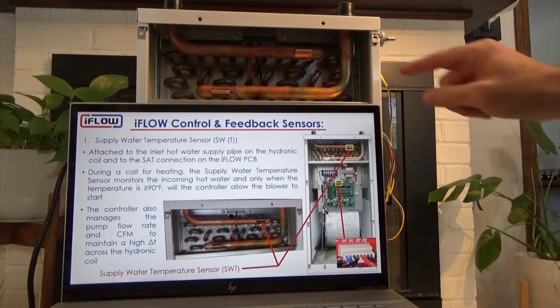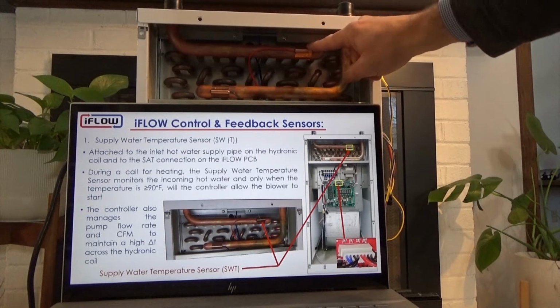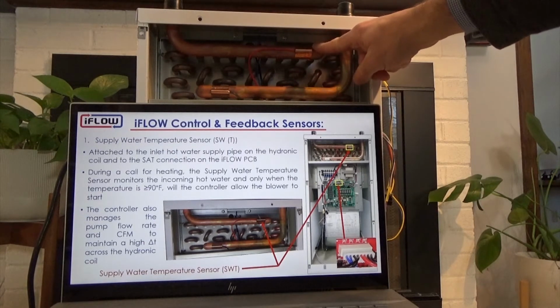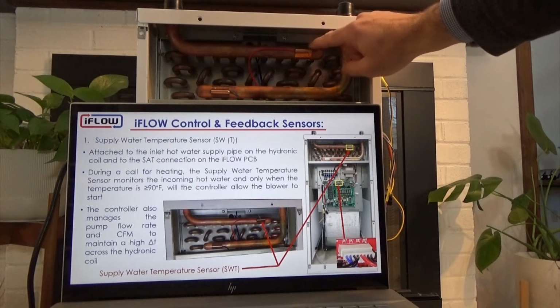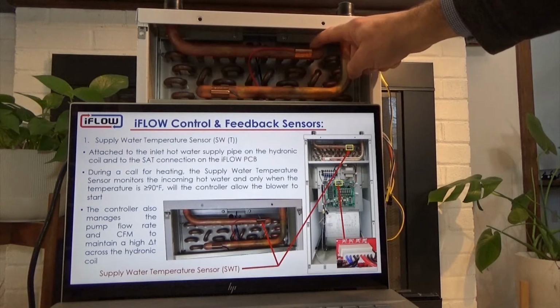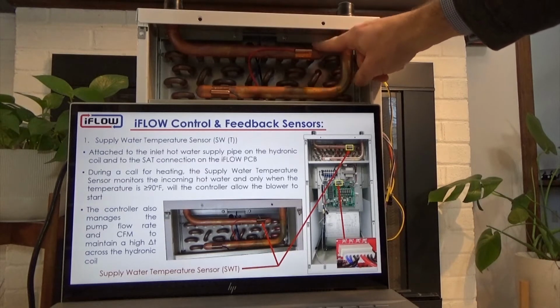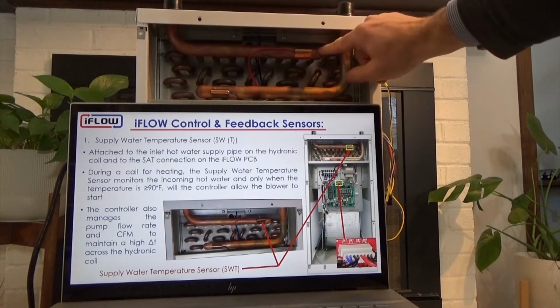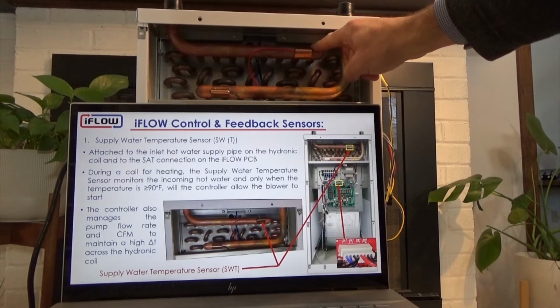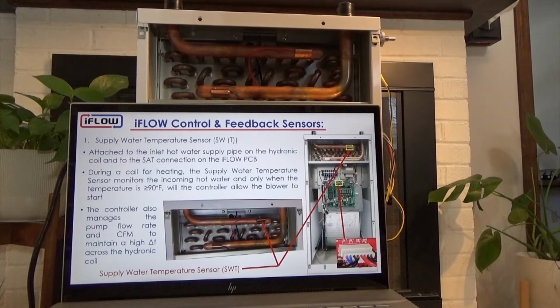During a call for heating, it's looking for a temperature of 90 degrees or above to be able to start the blower. If the supply water temperature from the heat source is below 90 degrees Fahrenheit, it's not going to turn on the blower until it gets that temperature, because it doesn't want to blow any cold air into the space.